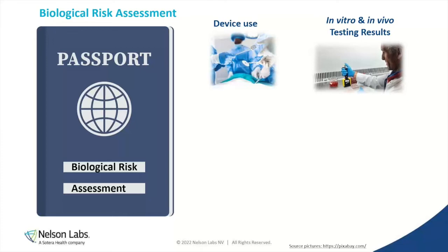So the first thing we're always going to talk about is device intended use. We talked about that at the beginning. How long is it contacting the patient? Is it used with only saline? Does it have only contact in the fluid paths? You can hear us getting those details ironed out. You would do that right up front in your risk assessment.